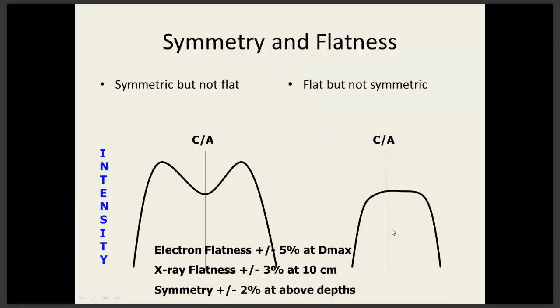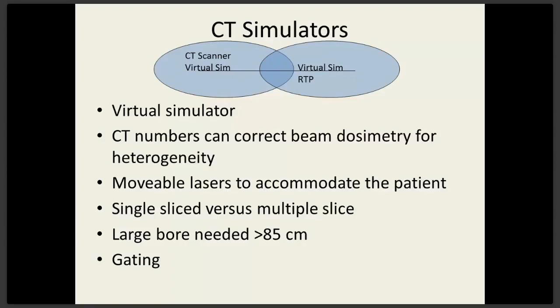Quick word about CT simulators. CT simulators not only give you the shape and size of the patient for treatment planning, but also give you the important CT number, which can be corrected for heterogeneity of the patient. So the simulator is a very important part of the treatment planning process. You've got the shape of the patient, the thickness, the organs that are all assigned values for organs at risk, but also CT numbers in the background, which correct the dose distribution for the heterogeneities within the patient. And here's an example of some of the fancy tattooing that we do here for localization. We've got a very talented group of therapists here, and they get a little carried away with their tattooing.